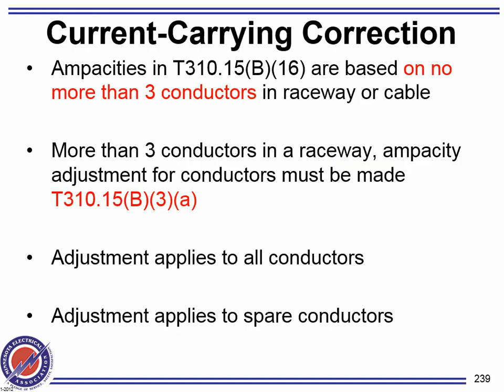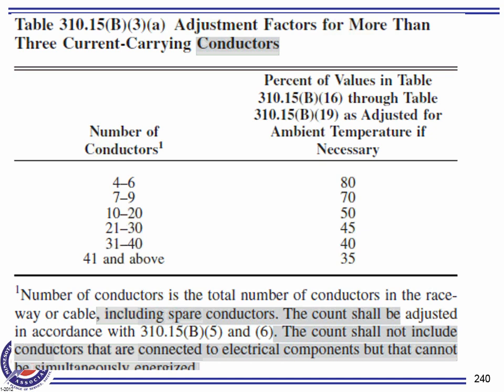Now, current carrying capacity. The NEC code book, guys, when you have a cable, they all have heat on them. Heat is enemy number one of electricity, right? So they will fail. Conductor insulation would deteriorate over time, and it will fail and short to ground fault. Okay, so here's the table that you use. If you have never seen that one, again, you're a plumber, but make sure you go highlight that one and know how to use it.